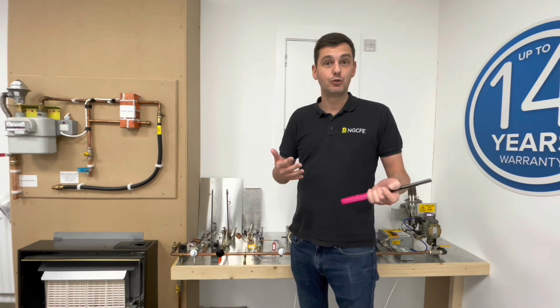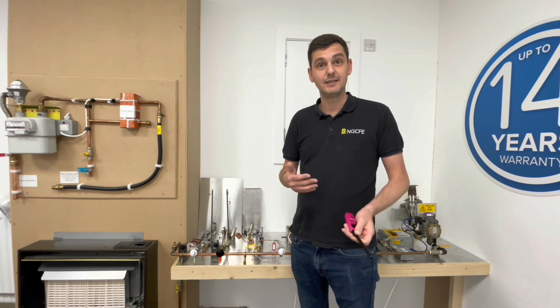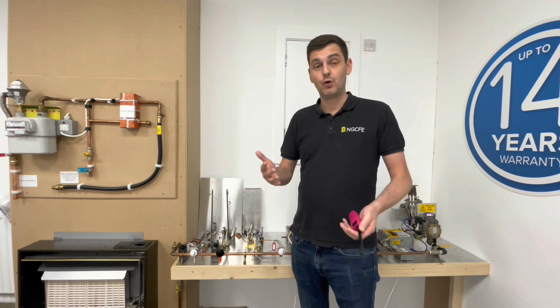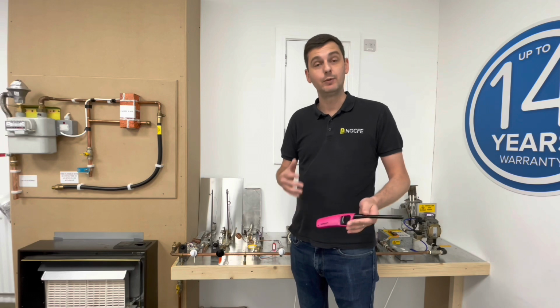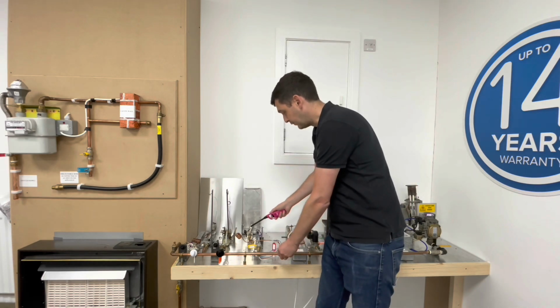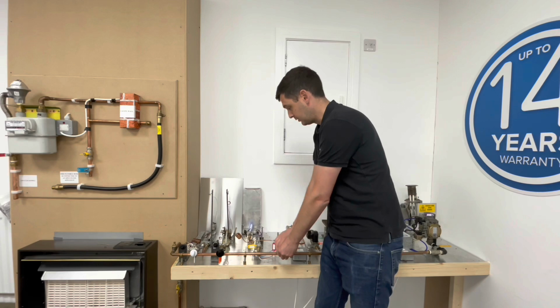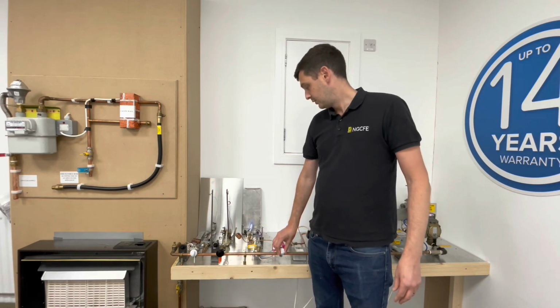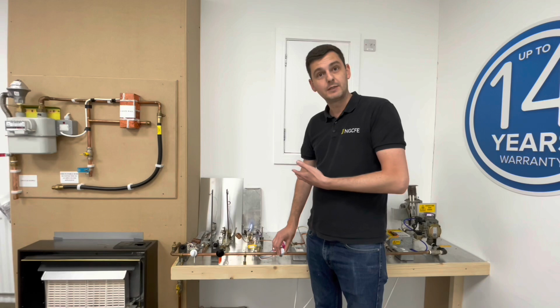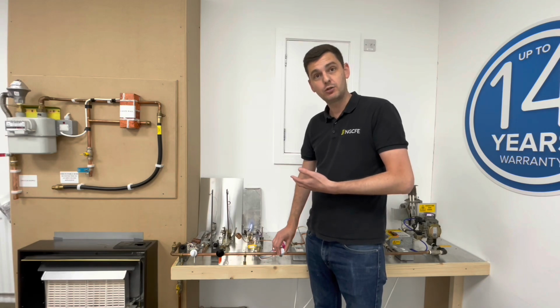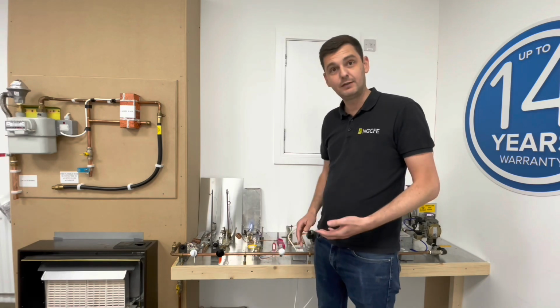So types of interrupter could be thermostats, like overheat stats, or commonly in boilers we'll see high limit stats or overheat stats. On older single point water heaters, these were quite common. We had the interrupter wired into the thermoelectric valve. So let's look at one in operation. Just as before, the same setup that we used on our safety shut-off valve. We're now allowing the thermocouple to heat up. Once the thermocouple's hot, we can then let go of the valve. The magnet is now holding the valve open fully.